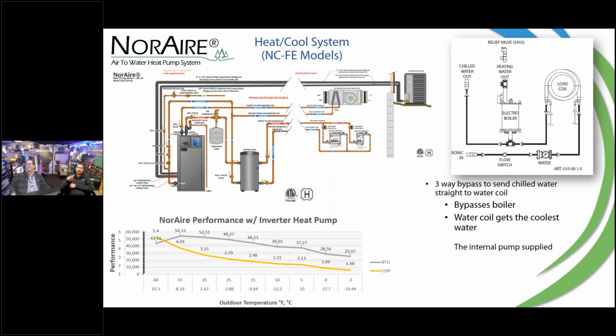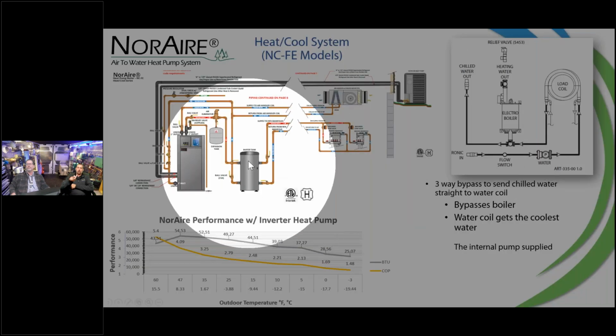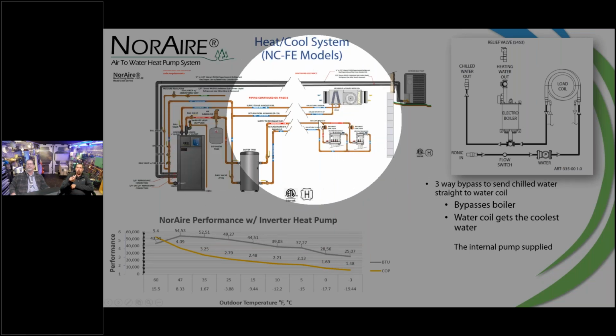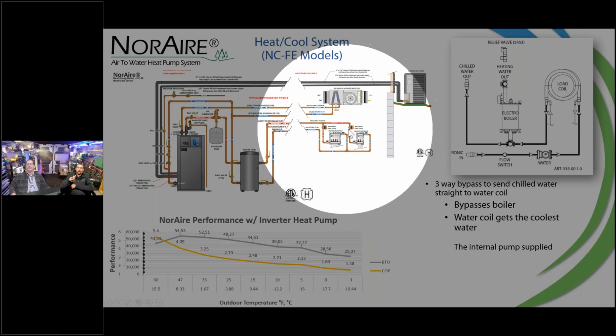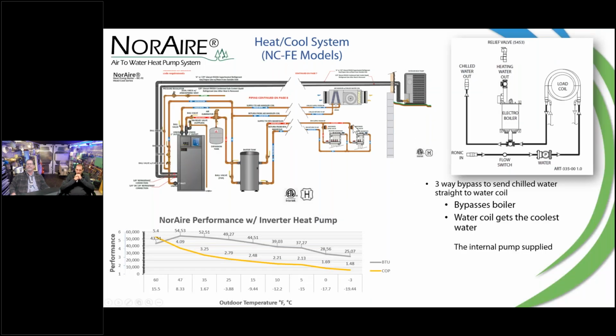We see the addition now bringing in a buffer tank, right, so that's our thermal storage. So we're going to start to make some BTUs, store them in that tank. You can see leaving this tank, and we're going to feed our low mass, or our radiant, low temp system.